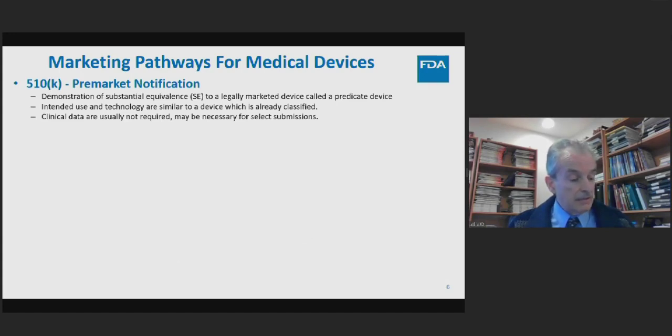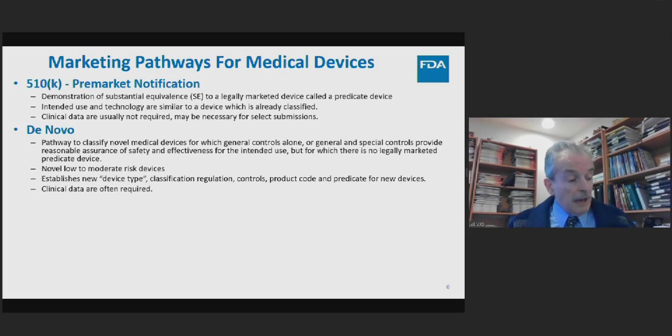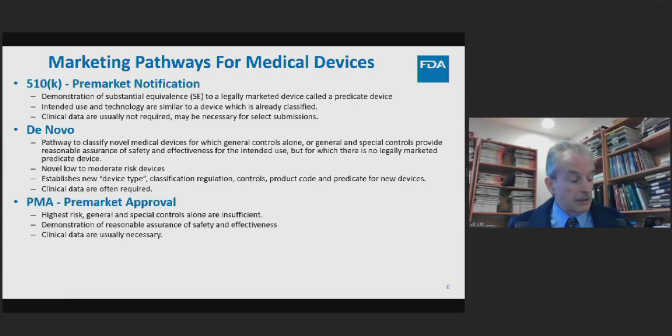Our goal in this pathway is for the submission to demonstrate that a new device is substantially equivalent to a legally marketed device called a predicate. Although performance data are typically required for traditional 510Ks, clinical performance data are requested only for a small number of submissions. The de novo pathway is used when the risk level of the device does not warrant the pre-market approval pathway, but the sponsor and FDA are unable to identify predicate devices to support 510K substantial equivalence. Granting of a de novo classification request authorizes marketing of the device in the US and also creates a new classification regulation. The pre-market approval pathway is reserved for the highest risk devices and requires that the sponsor provide valid scientific evidence to support a reasonable assurance of safety and effectiveness.